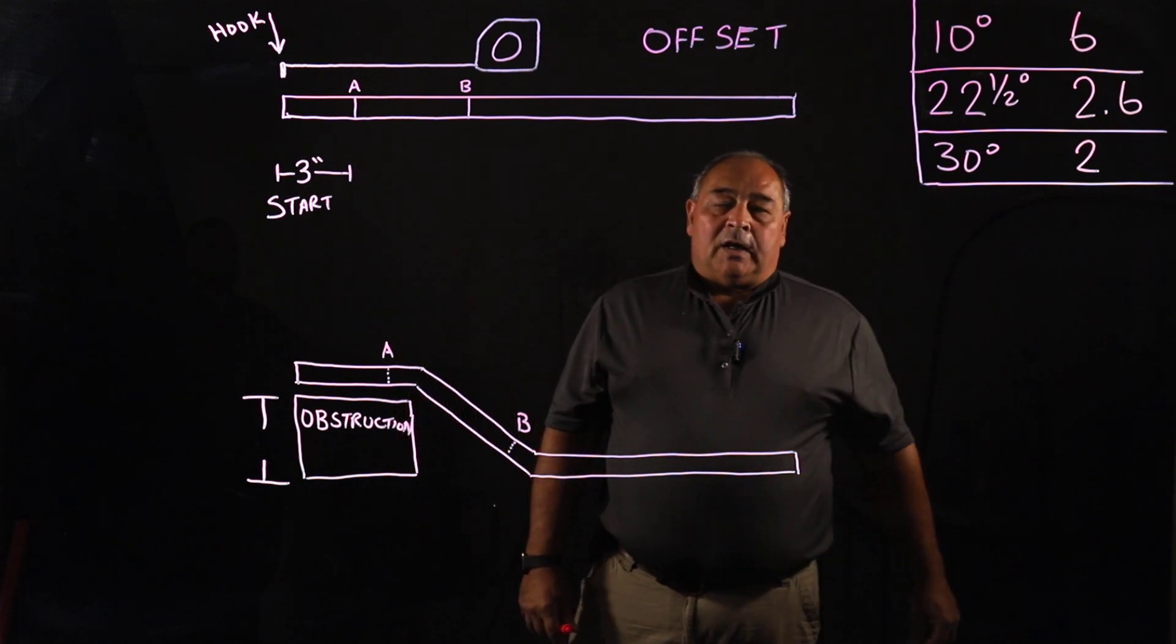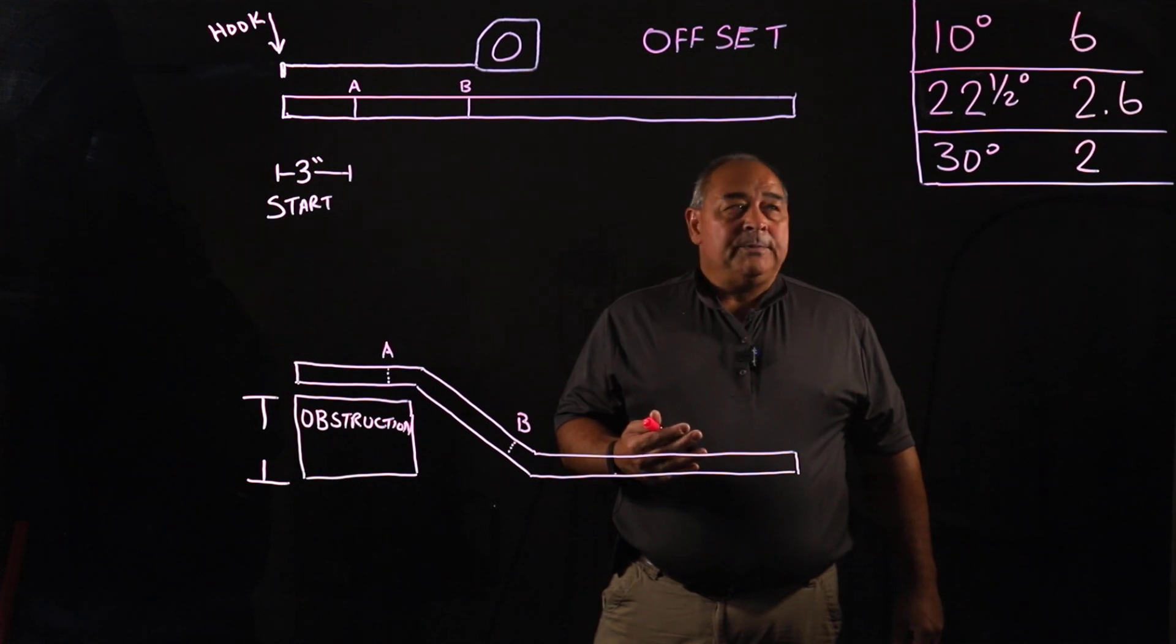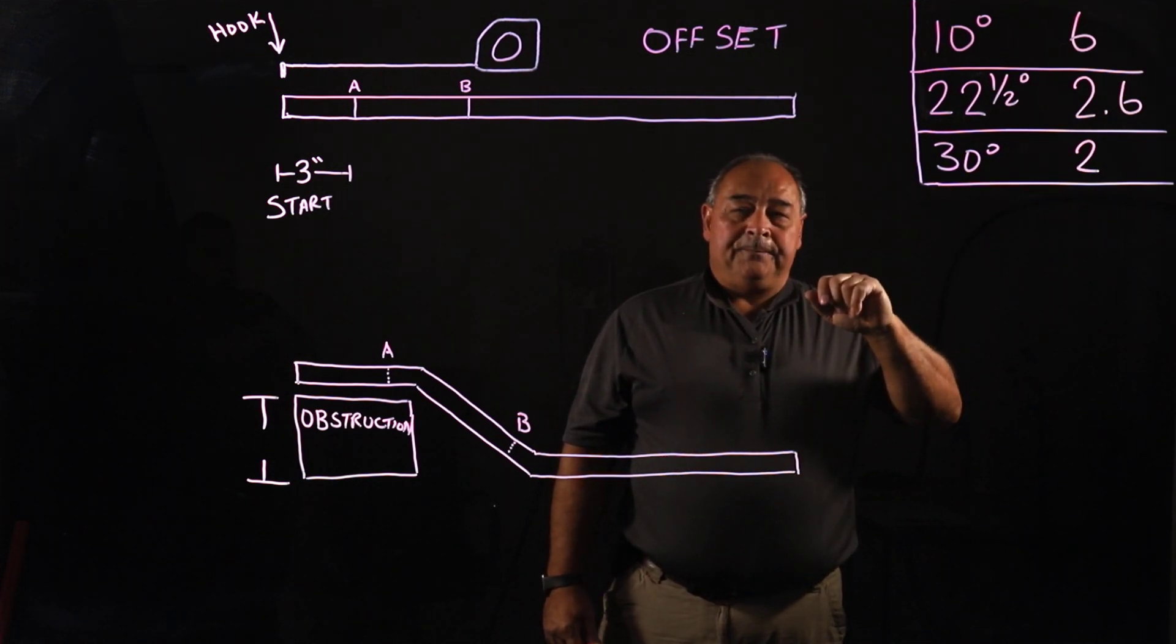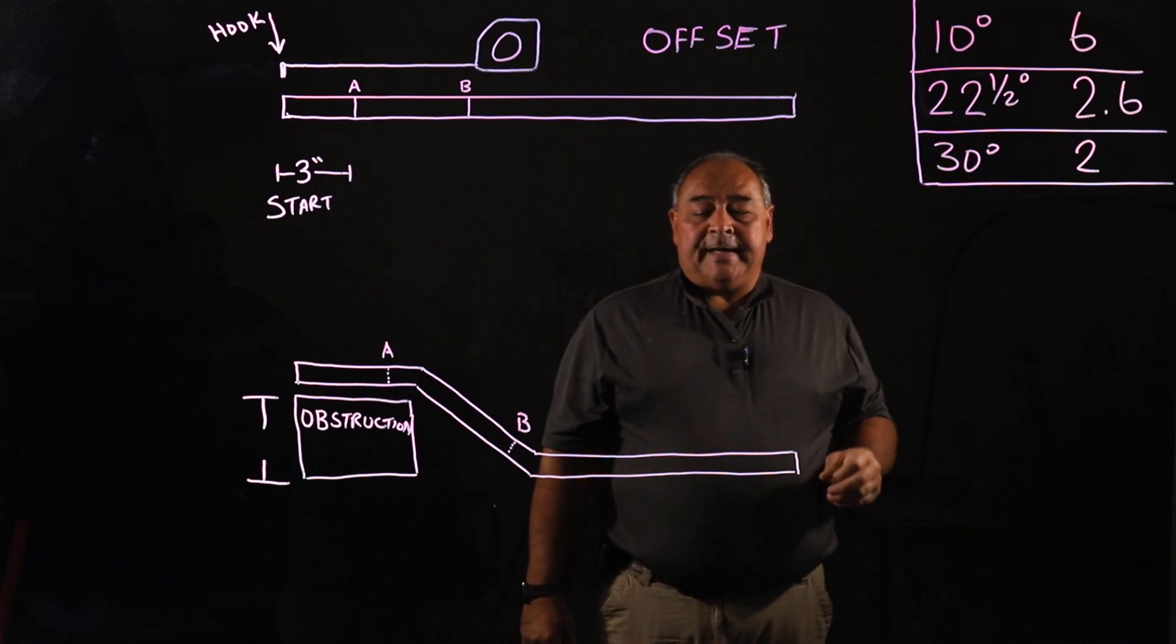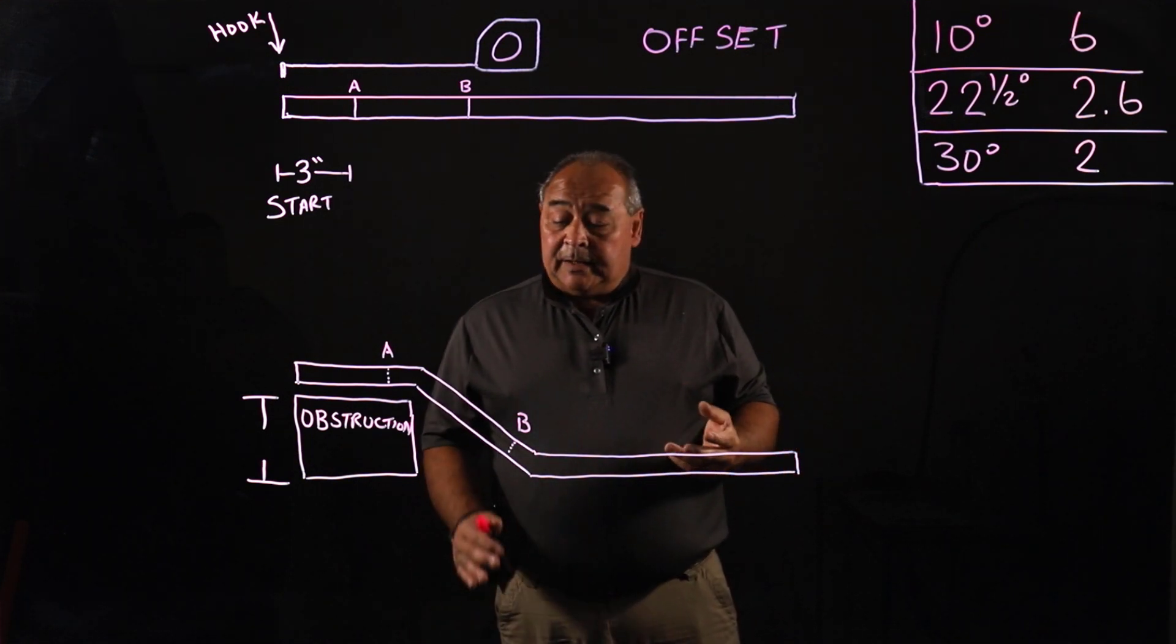Our 22 and a half is kind of an oddball. If we're going to 22 and a half, most people would rather just go to a 30. There's a reason for 22 and a half for some certain purposes, depending on your design and your wishes. But your multiplier for a 22 and a half would be 2.6.